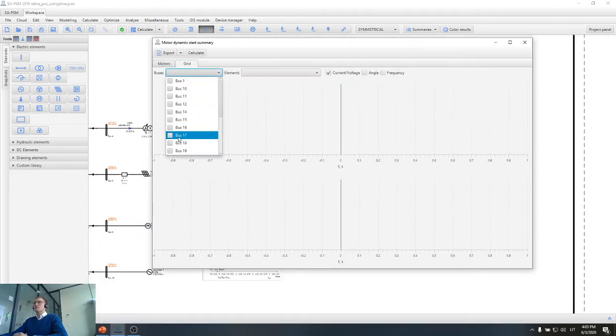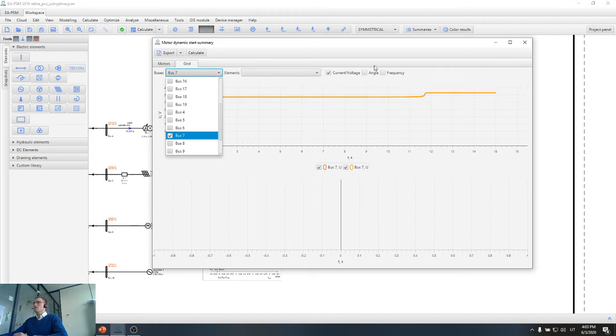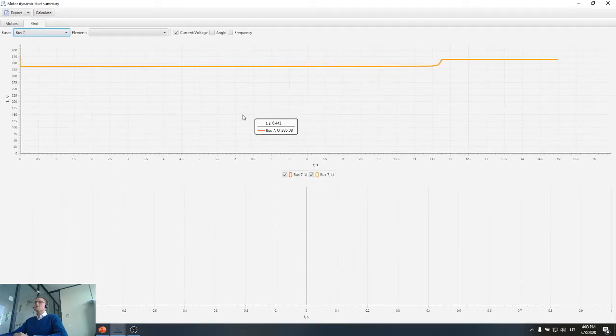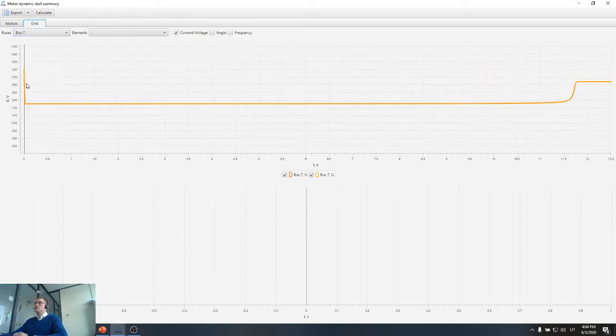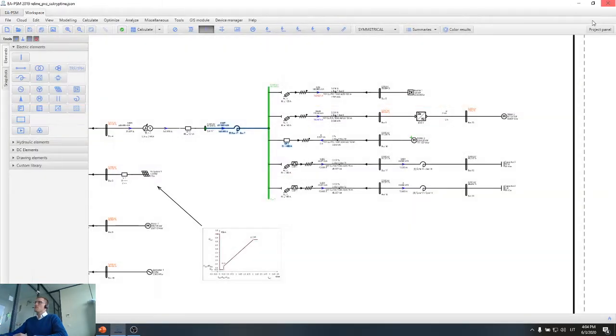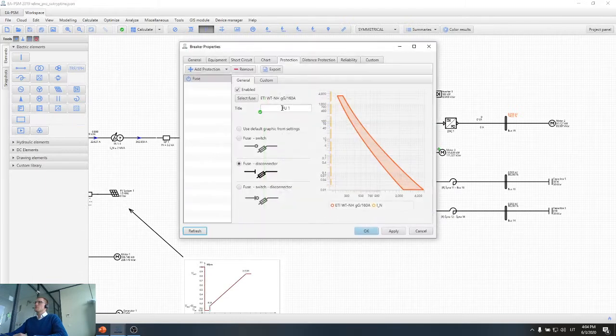So bus bar 7, yeah. In case of bus bar 7, we can see that during motor starting, the voltage was around 334 volts. But after some time, after the motor was started, the voltage went back to normal. So this graph explains the voltage dip phenomena during motor starting, and all the other currents during this motor starting will increase.